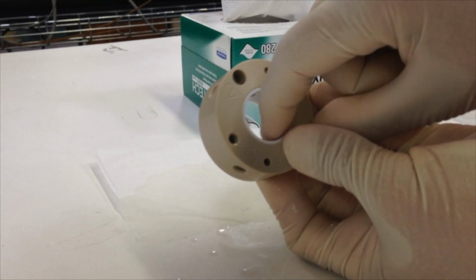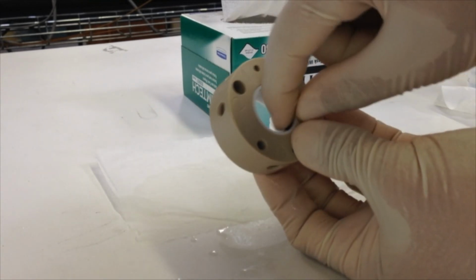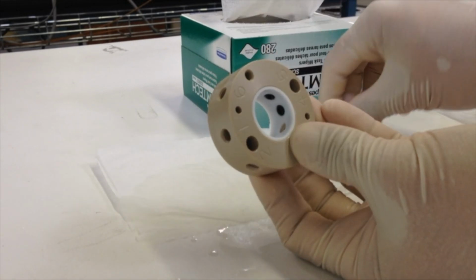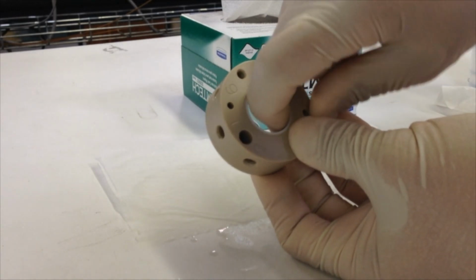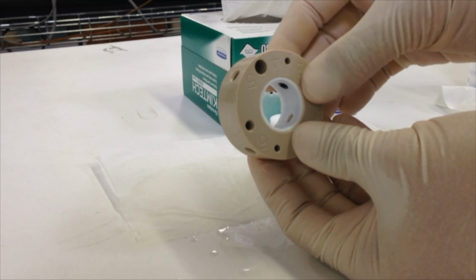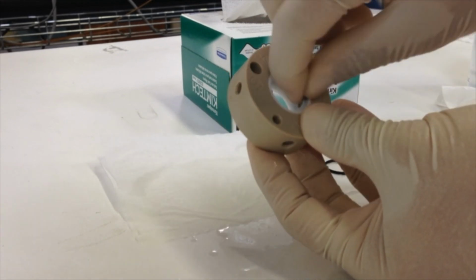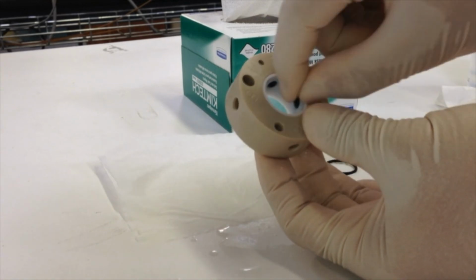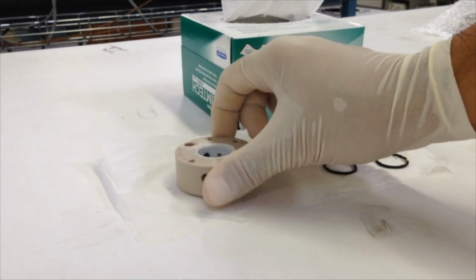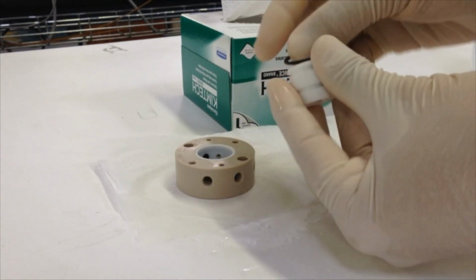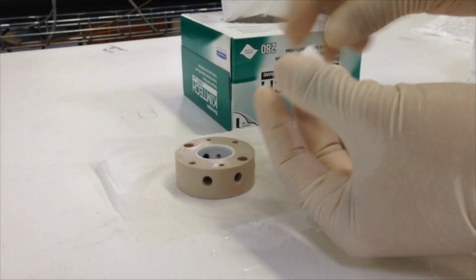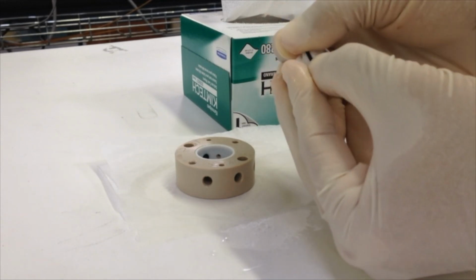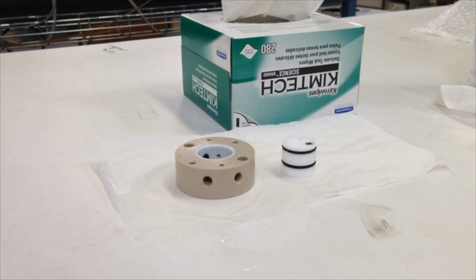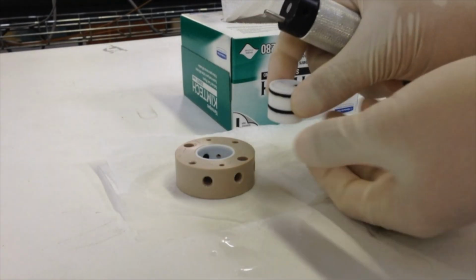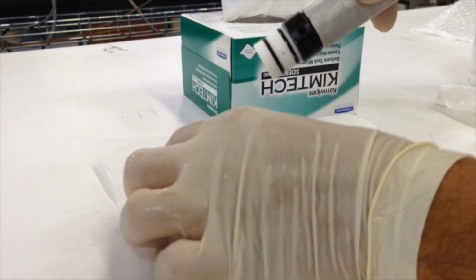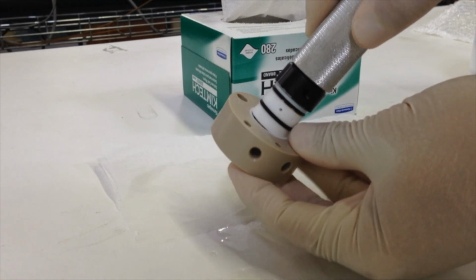Next, push in the 5 small O-rings with your fingers. Slide on the 2 valve insert O-rings. Use the valve tool to push the valve insert into the valve face. The valve tool will make sure the valve insert is flush with the valve face.